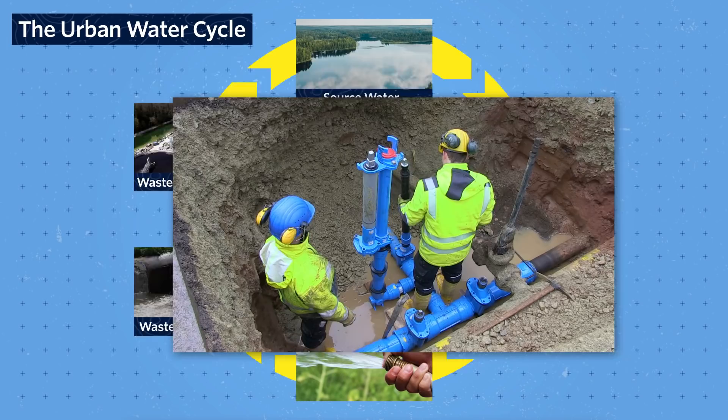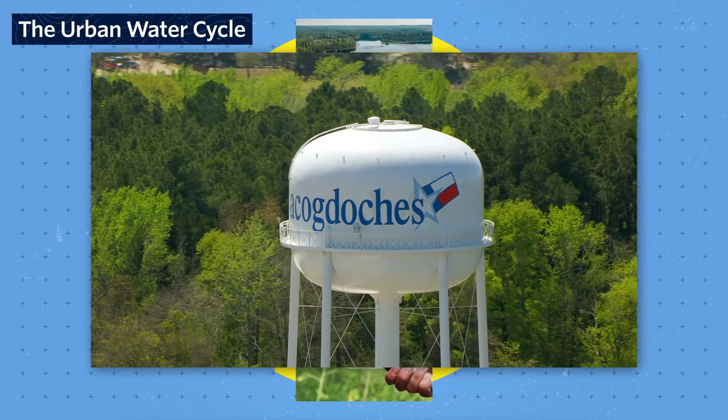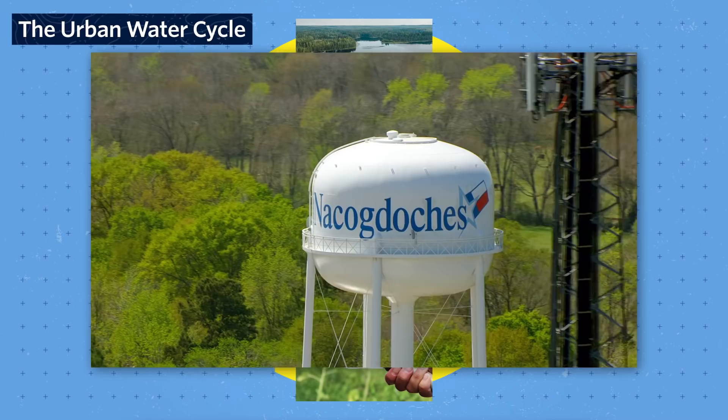After treatment, the clean water enters the water distribution system — a network of pipes, pumps, and storage facilities. Pumps push water uphill and ensure a constant and appropriate level of water pressure in the pipes. Water towers serve a dual purpose: they act as clean water storage tanks and also help provide water pressure. They are able to supply pressurized water during a power outage, though not indefinitely, as a powered pump is required to refill the tower. They can also be used to provide pressure during peak water and peak power times, and refilled by a pump when electricity costs are lower.